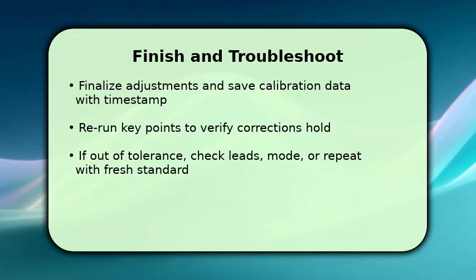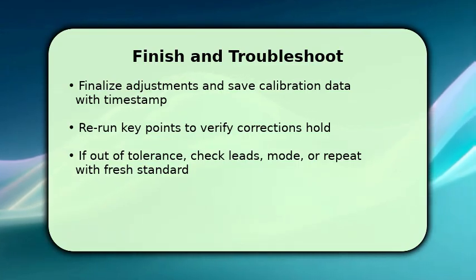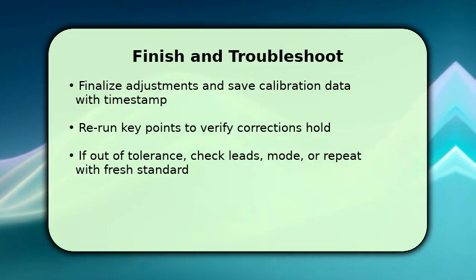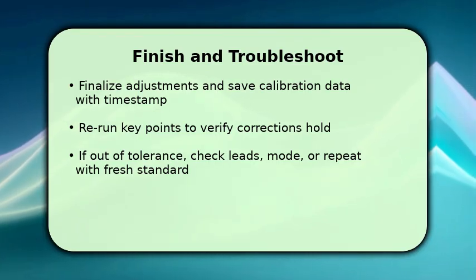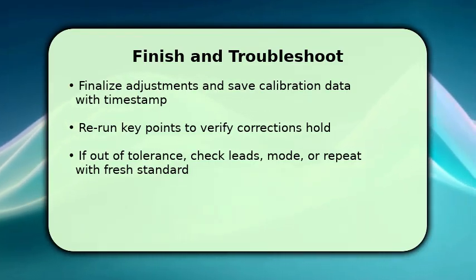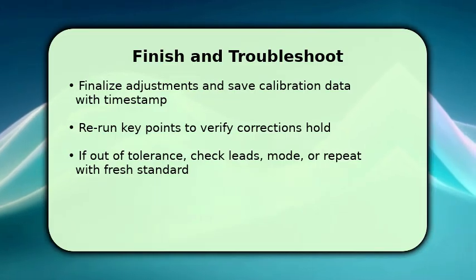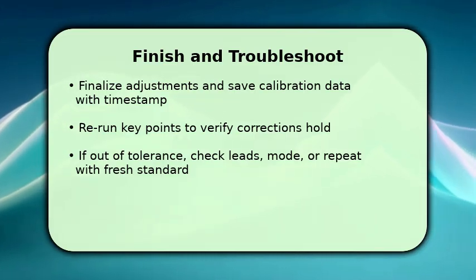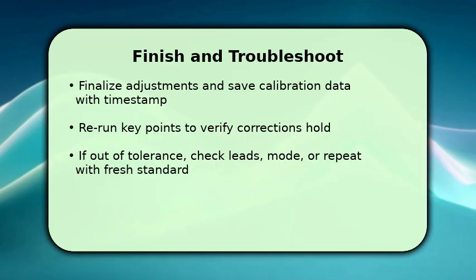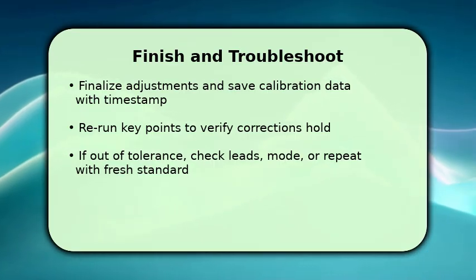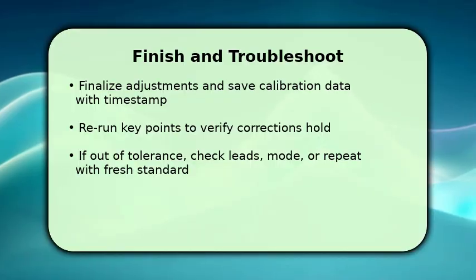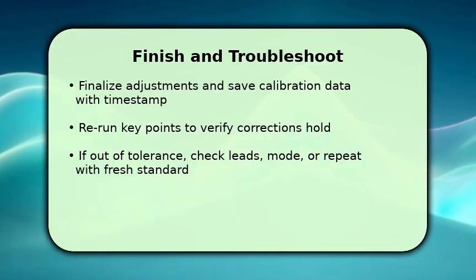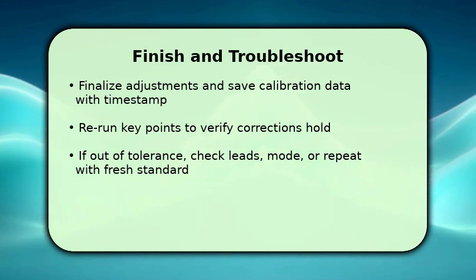You complete the process by applying final corrective adjustments indicated by your measurements, then save the calibration data with a timestamp and identifier so it's auditable. Once done, rerun a few key reference points to verify corrections are stable. This confirms the fix worked rather than masking a transient. If readings remain out of tolerance, check common culprits: bad leads, incorrect measurement mode, or a worn reference standard. As a troubleshooting tip, replace or recertify the standard first. Many errors trace back to the reference.